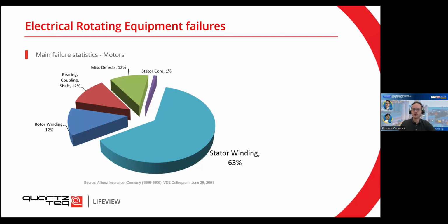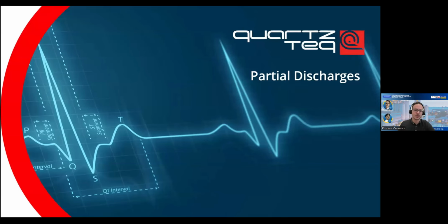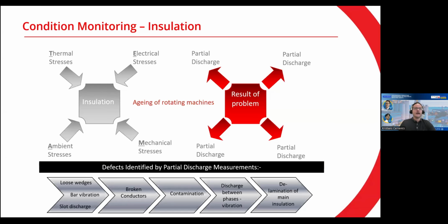So to start with the first one, partial discharges. Partial discharges are related to the stator winding failures. This is the most common type of failure, and this is also the most common type of condition monitoring. As I mentioned before, machines are always exposed to external stress. It can be thermal stresses, increases or decreases in temperature, or electrical stresses. It can also be ambient stresses, for example some moisture on the machine, or you can have mechanical stresses, so something is not fixed in place and there's a lot of vibration. And all these issues can lead to defects in the machine.